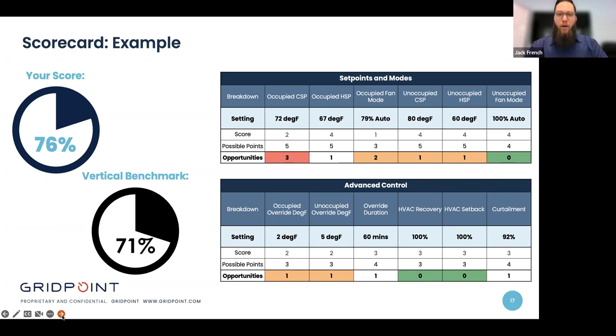So I'm not going to go through every single one of these settings and how the scores are allocated. I believe that is pretty straightforward, but looking at the areas of opportunity, we have occupied cooling set point, which we talked about. Of these 24 units, 79% of them were set to auto mode. So there's opportunity there. 21% of the units were set to on 24/7 during the occupied period. During their unoccupied period, on the flip side, all of them were set to auto, which is at best practice.